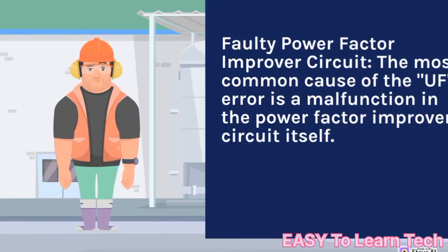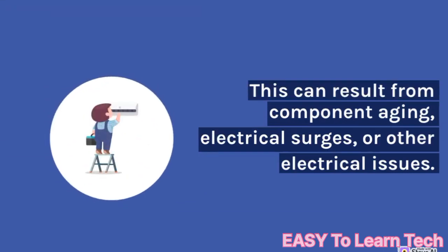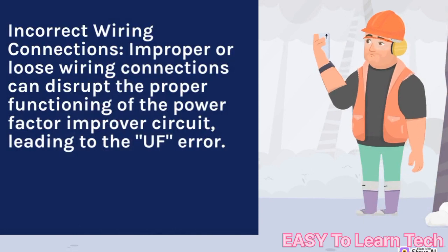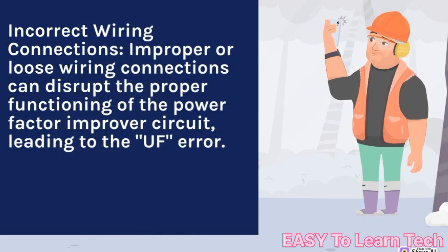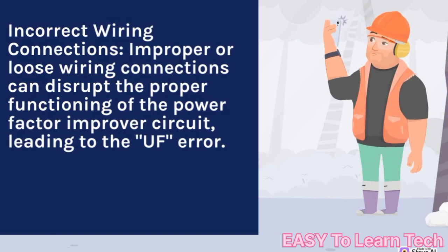Faulty Power Factor Improver Circuit: the most common cause of the UF error is a malfunction in the Power Factor Improver Circuit itself. This can result from component aging, electrical surges, or other electrical issues. Incorrect wiring connections — improper or loose wiring connections can disrupt the proper functioning of the Power Factor Improver Circuit, leading to the UF error.